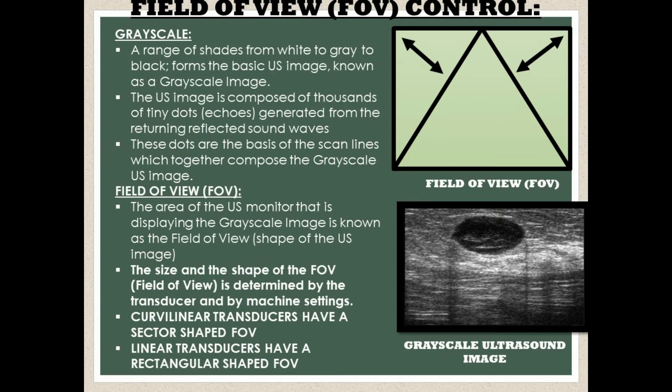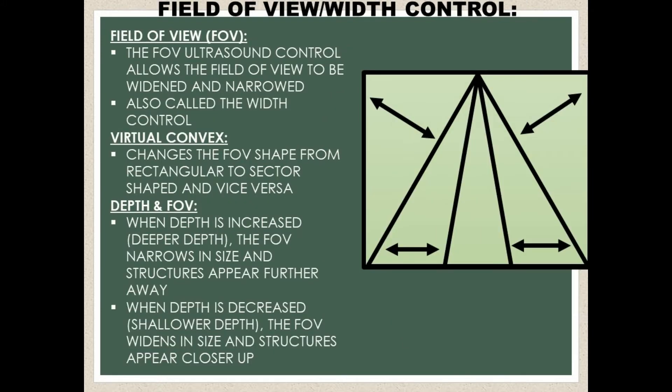Curvilinear transducers have a sector-shaped field of view, and linear transducers have a rectangular-shaped field of view. The field of view ultrasound control allows the FOV size to be widened and narrowed on the ultrasound image, and it's also known as the width control. There's also an ultrasound control called virtual convex, which changes the field of view shape from rectangular to sector shape, and vice versa.